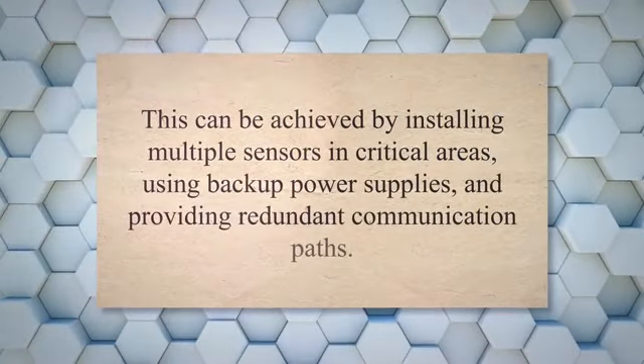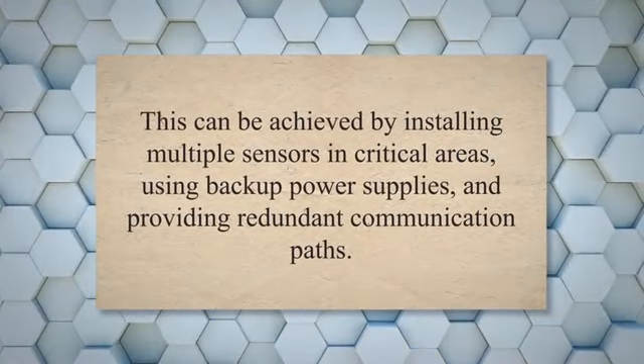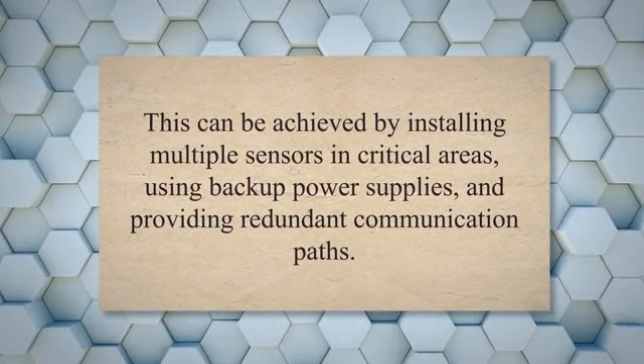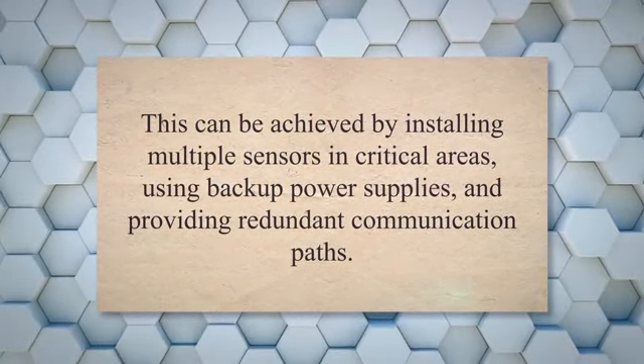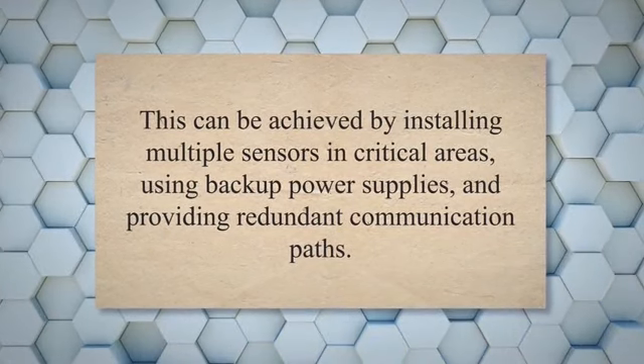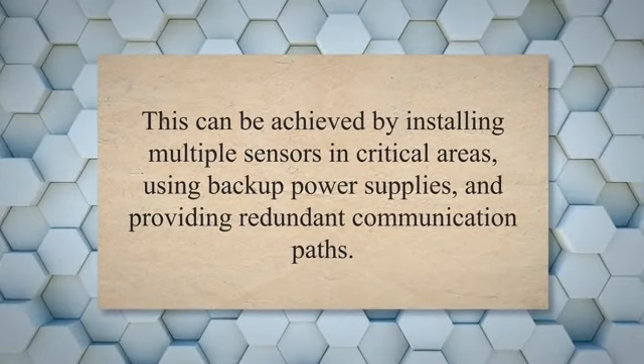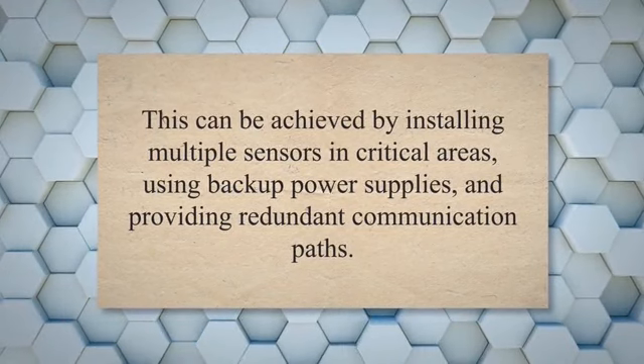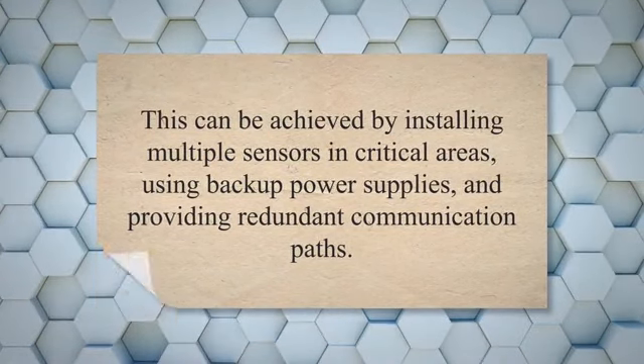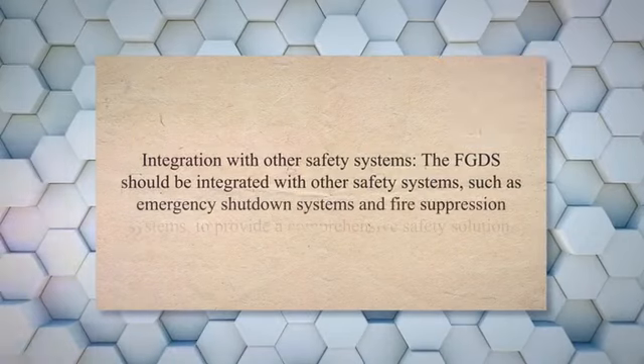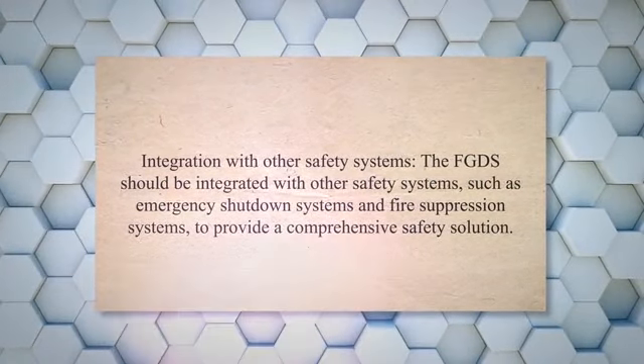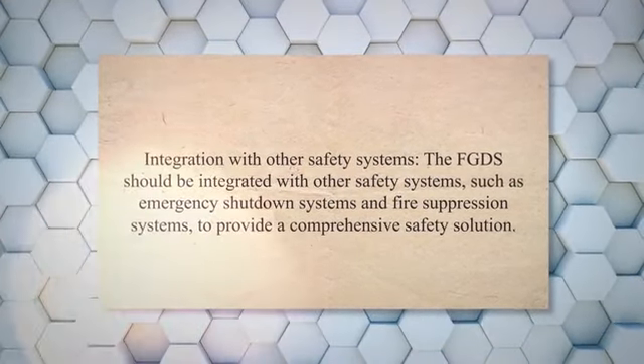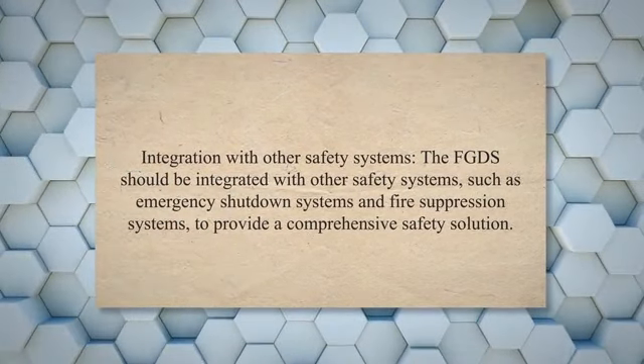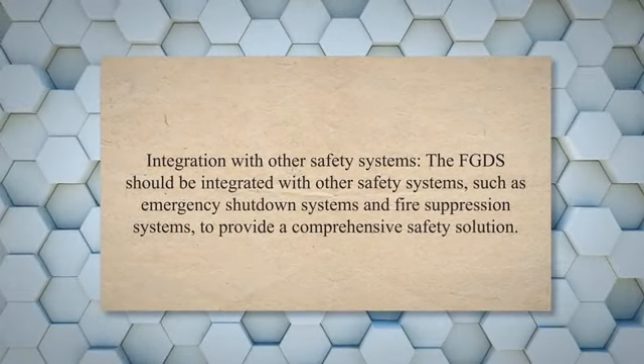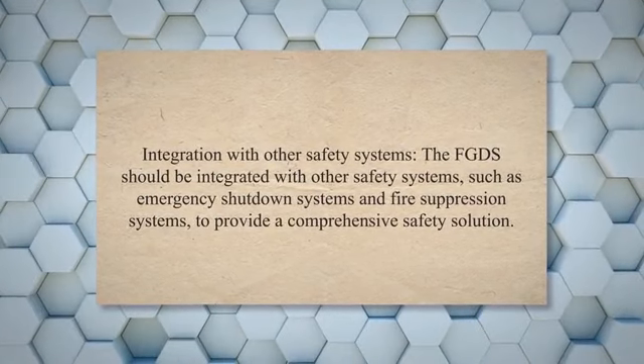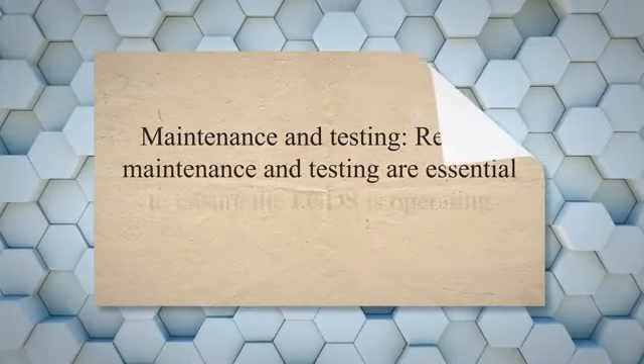System redundancy. Redundancy is essential to ensure that the system continues to function even if one or more sensors or components fail. This can be achieved by installing multiple sensors in critical areas, using backup power supplies, and providing redundant communication paths. Integration with other safety systems. The FGDS should be integrated with other safety systems, such as emergency shutdown systems and fire suppression systems, to provide a comprehensive safety solution.